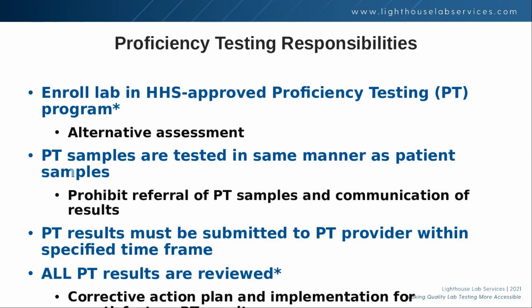For all proficiency testing samples, the lab director ensures that they are tested in the same manner as patient samples, that they are not referred to another laboratory, and that results are not discussed prior to evaluation. The lab director will also need to coordinate with lab staff to ensure that the proficiency testing results are submitted in a timely manner. Once the evaluation of results is received from the proficiency testing provider, the lab director should review all results and perform any necessary corrective and preventative action for any analytes that are considered unsatisfactory. Oftentimes, this will require the involvement of the technical and general supervisor and the person who actually performed testing on the proficiency testing samples to determine the root cause of failure.